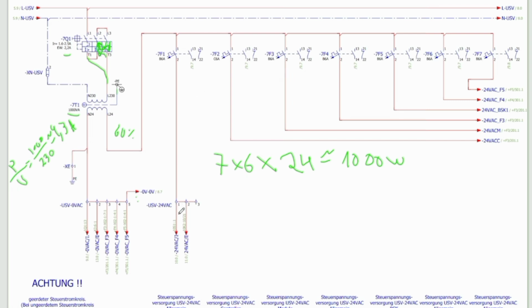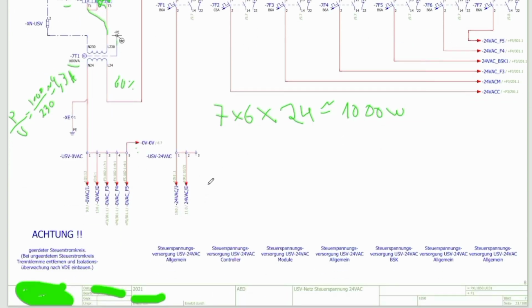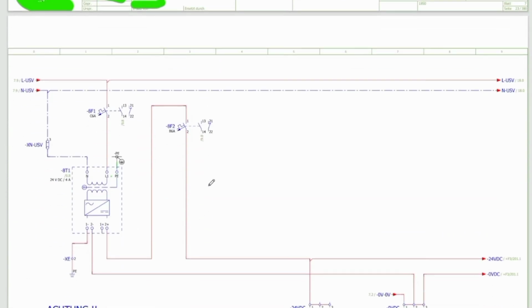Going to show you one more small thing. It's 6 amps on the high voltage side from the transformer and rectifier. In this case, it must be, and it is, a switching power rectifier, power electronics, and 6 amps in the low voltage protection. This is not doable, it's not possible, you're not protecting anything.